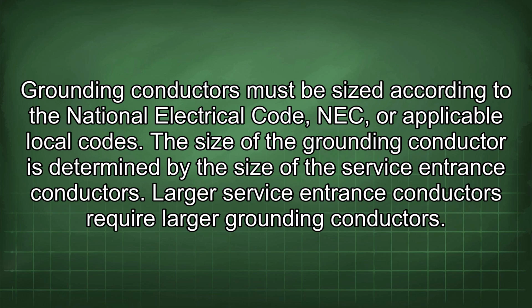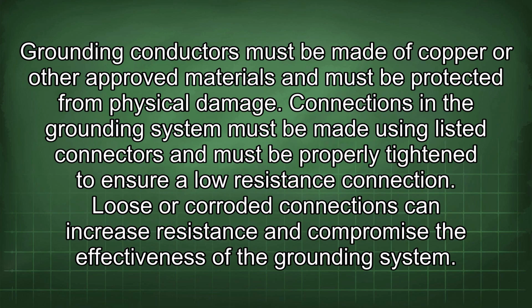Grounding conductors must be sized according to the National Electrical Code (NEC) or applicable local codes. The size of the grounding conductor is determined by the size of the service entrance conductors. Larger service entrance conductors require larger grounding conductors. Grounding conductors must be made of copper or other approved materials and must be protected from physical damage. Connections in the grounding system must be made using listed connectors and must be properly tightened to ensure a low resistance connection. Loose or corroded connections can increase resistance and compromise the effectiveness of the grounding system.